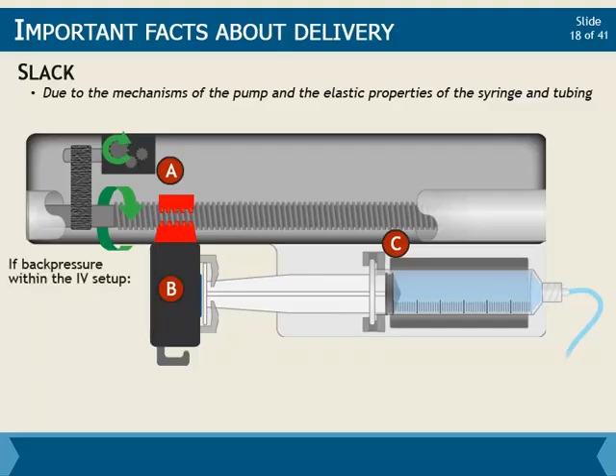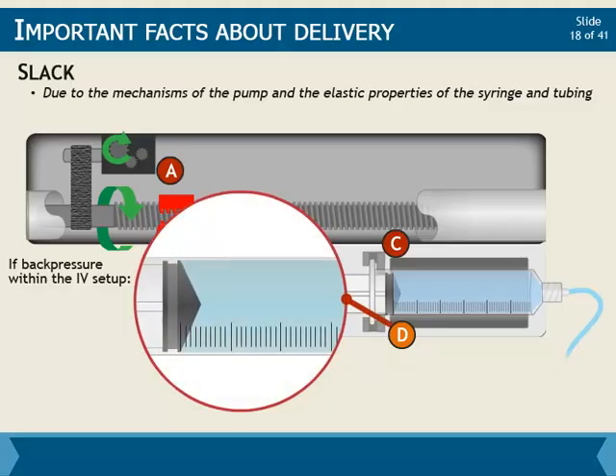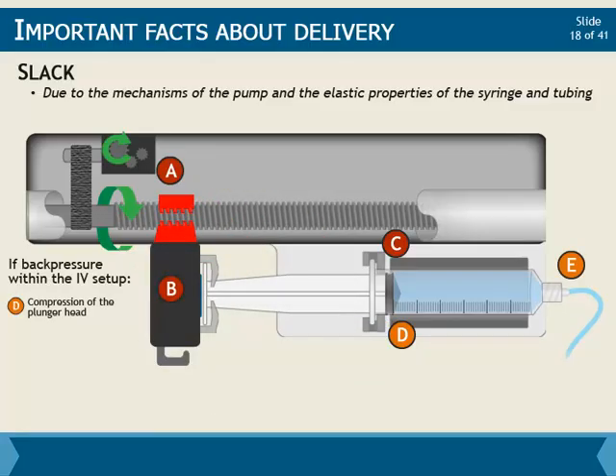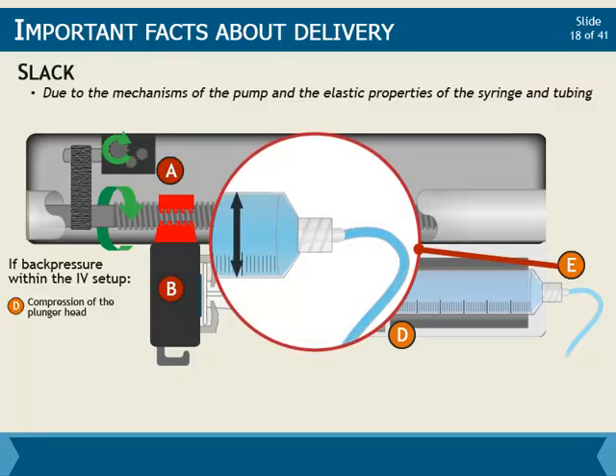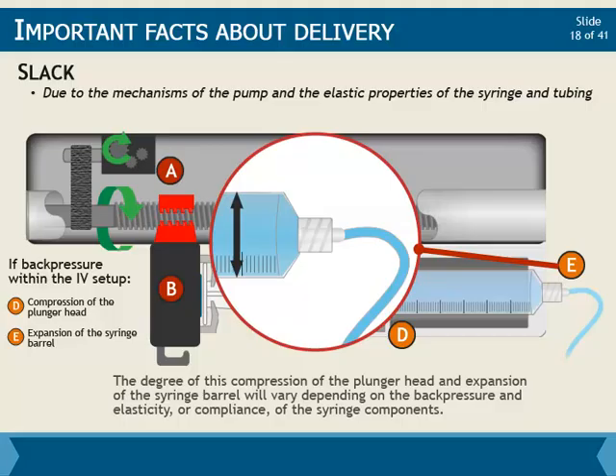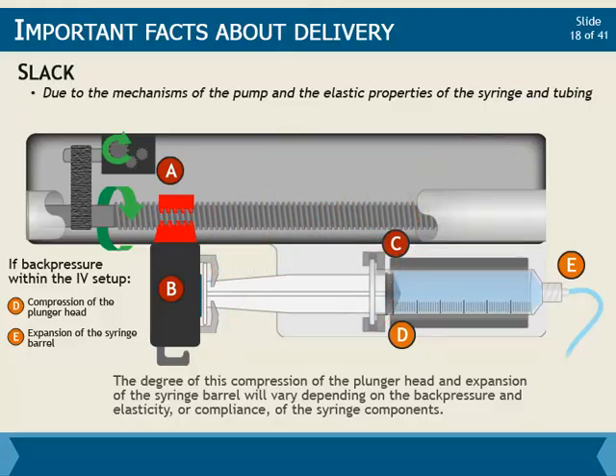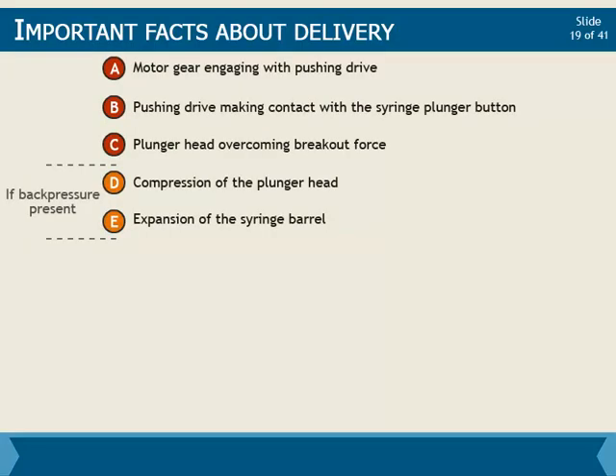Furthermore, if there is back pressure within the IV setup, it serves to actually oppose the flow of fluid to the patient. As a result, a few other events occur in response to back pressure before the fluid flows from the syringe. The plunger head is often soft rubber, and when it encounters back pressure, it will compress as the plunger starts to press on the fluid. In addition, as the syringe builds force to overcome this back pressure, the walls of the syringe barrel may expand. The degree of this compression of the plunger head and expansion of the syringe barrel will vary depending on the back pressure and elasticity or compliance of the syringe components. The more elastic the components and the higher the back pressure, the greater the delay. Only once all these events occur will fluid start to flow through the IV tubing to the patient.